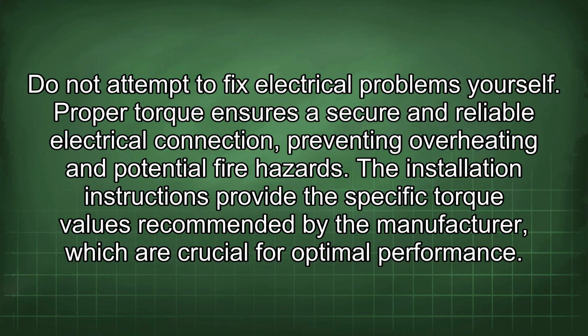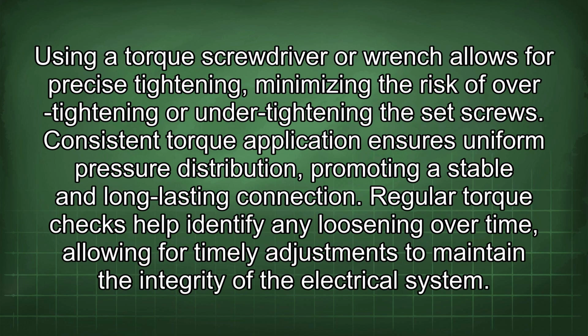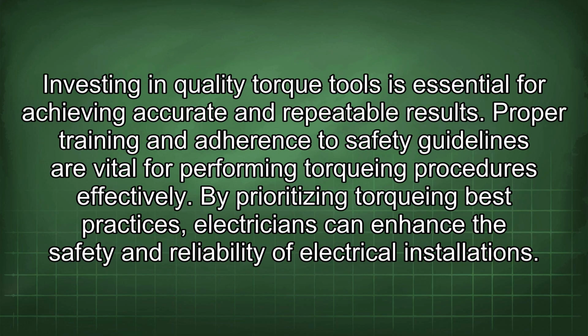Proper torque ensures a secure and reliable electrical connection, preventing overheating and potential fire hazards. The installation instructions provide the specific torque values recommended by the manufacturer, which are crucial for optimal performance. Using a torque screwdriver or wrench allows for precise tightening, minimizing the risk of over-tightening or under-tightening the set screws. Consistent torque application ensures uniform pressure distribution, promoting a stable and long-lasting connection. Regular torque checks help identify any loosening over time, allowing for timely adjustments to maintain the integrity of the electrical system. Investing in quality torque tools is essential for achieving accurate and repeatable results.